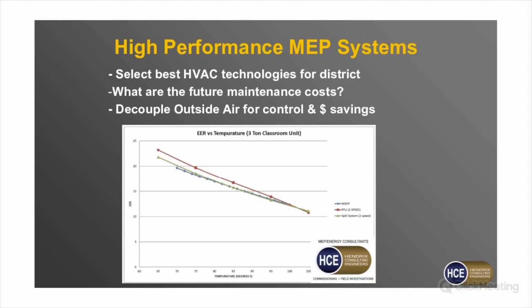In fact, this is a comparison that we looked at. It is efficiency ratings for a typical 3-ton classroom unit. So a lot of times we're going to see the outside air decoupled from the normal heating cooling unit for the classroom. And you can see we would apply them this way. So if you look at that water source unit, which is the blue line, you'll see as the temperature on the bottom gets colder, the efficiency goes up. So we got the efficiency on the y-axis and the temperature on the x-axis.